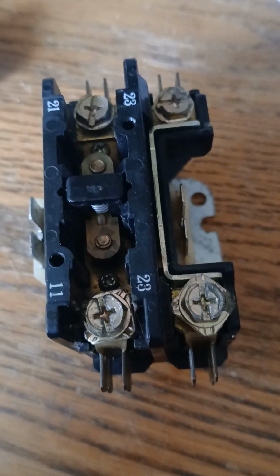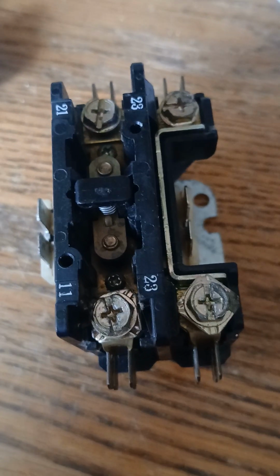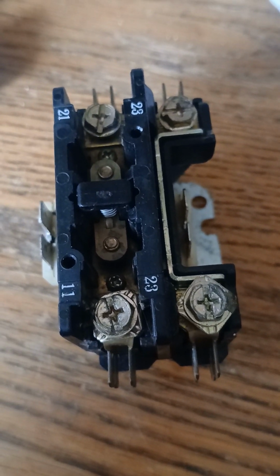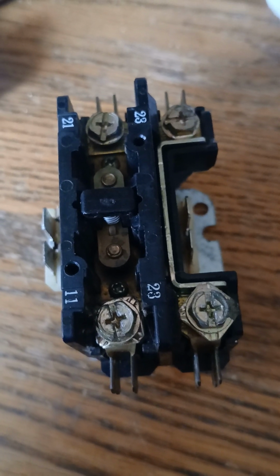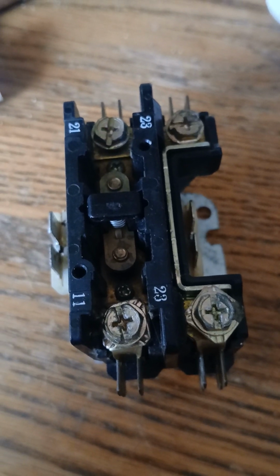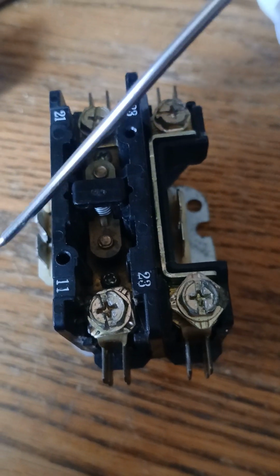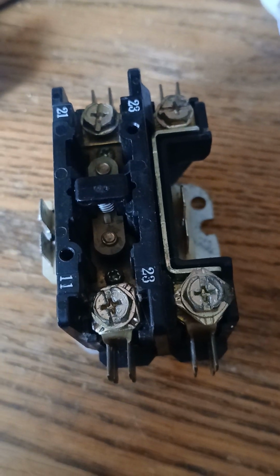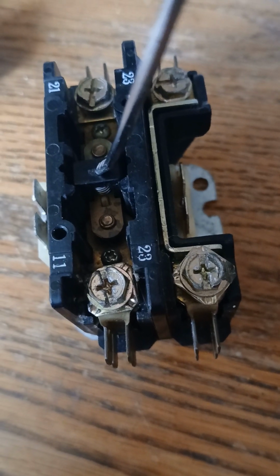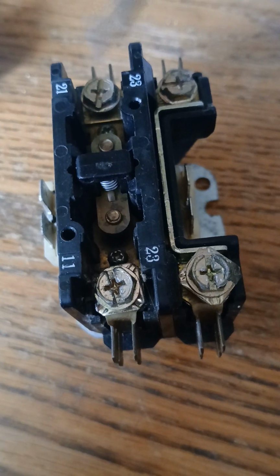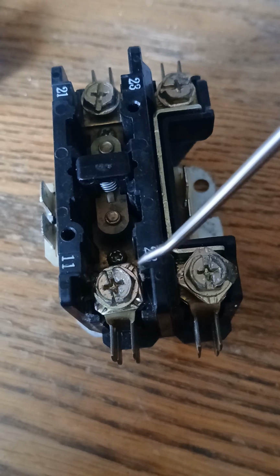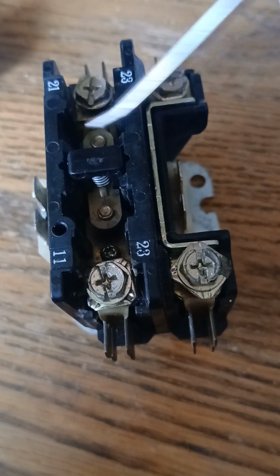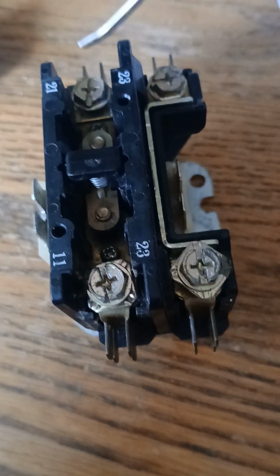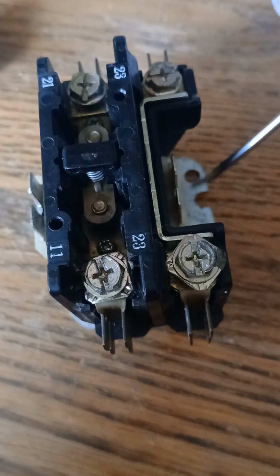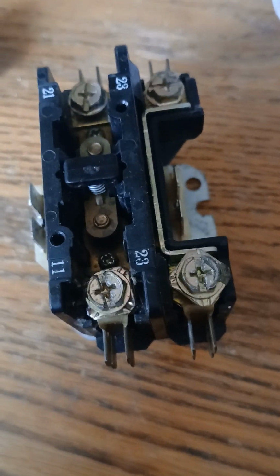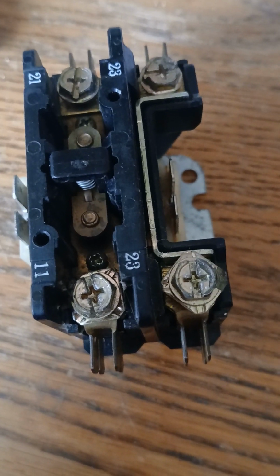But what happens when the thermostat de-energizes and it satisfies itself? Say, for instance, we were looking to get the temperature to 70 degrees, and that would be the set point. Once the set point arrives at 70 degrees, the thermostat would cut off. Once it cuts off, the low voltage power stops here. Once the low voltage power stops here, the contactor, which conveyed the voltage from one side to the other, would simply come up, and if the contactor's working properly, one would have voltage here, no voltage here. If the contactor's energized, it pulls this in. Once it pulls in, you've got high voltage here, 120 here, 120 here, and on the side is the coil.